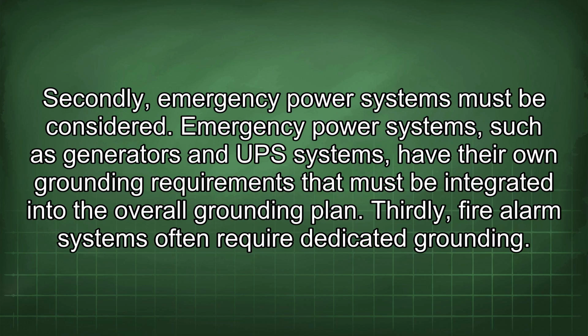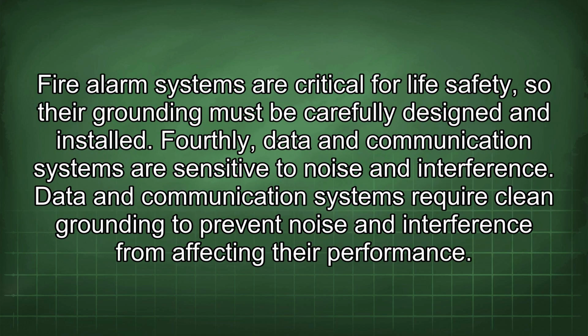Secondly, emergency power systems must be considered. Emergency power systems, such as generators and UPS systems, have their own grounding requirements that must be integrated into the overall grounding plan. Thirdly, fire alarm systems often require dedicated grounding. Fire alarm systems are critical for life safety, so their grounding must be carefully designed and installed. Fourthly, data and communication systems are sensitive to noise and interference. Data and communication systems require clean grounding to prevent noise and interference from affecting their performance.